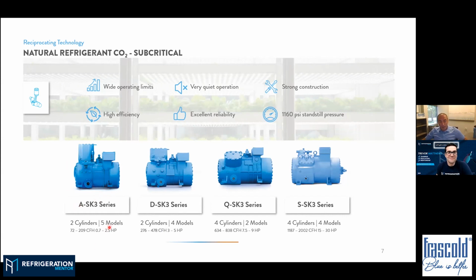So we go from a small 2.5 HP on the A series subcritical, then we arrive to the newest S model that has a 30 HP motor and 2000 CFH. What are the main characteristics of this compressor? They are all splash lubricated, so they don't have an oil pump at all. And the standstill pressure is 1160 psi. That is quite standard for subcritical applications and for the ambient temperature reachable in a machine room.